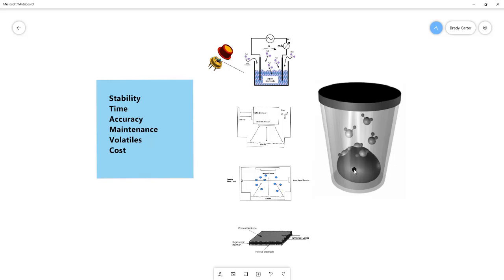The requirements set to indicate that equilibrium has occurred can also vary. So this means the only way to track equilibrium is to know that you're at a static state, so there aren't any changes over time. What's used is a setting that looks at water activity values over time, and when the variation drops to a certain preset level, that indicates the end of the test. The more stringent you set that, the more likely you are to have equilibrium, but it also extends the test time. So if there are differences between those settings, it will result in differences in analysis times.